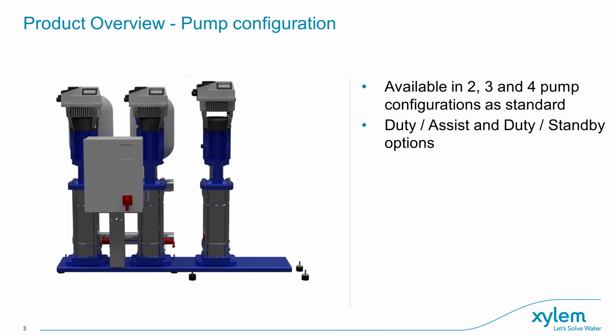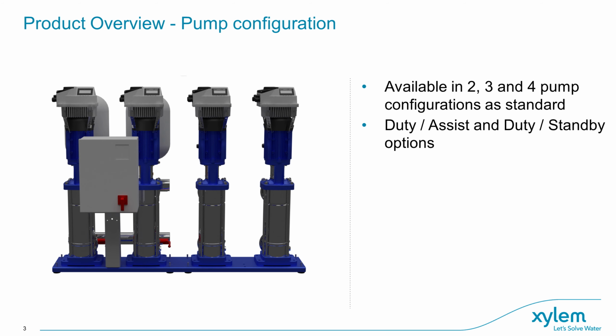It comes in multiple pump configurations with twin, 3 and 4 pump booster sets available as standard, and the sets could be sized and set up to either run in duty assist or duty standby, depending on your application. In many commercial building services applications, it is common to have at least one standby pump working alongside one or more duty pumps.